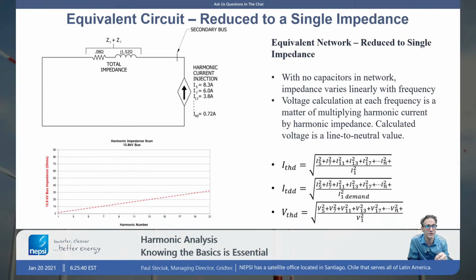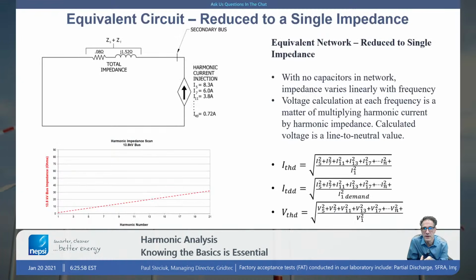Total harmonic distortion is an instantaneous value. What are you getting at this moment? Okay, so it's just putting the fundamental in the denominator, the fundamental frequency at that moment in time, and all the harmonic currents at that moment in time. And so using these calculations, we can come up with those various distortion values. Down here on the lower left is a very simple impedance scan.